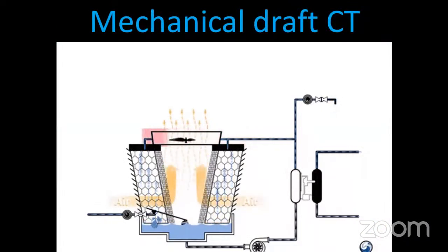So this is the mechanical draft cooling tower. That is, it requires an active fan. Actually, see this, sir. The air enters through the louvers, and it's a cross flow, and during crossing this cooling tower, the water flows downwards and the air takes away the heat from that water, and theoretically only the hot air goes up. Actually, it doesn't happen. The hot air with water vapor goes up, so that losses are significant. We'll see it. It's a cross flow type, sir.